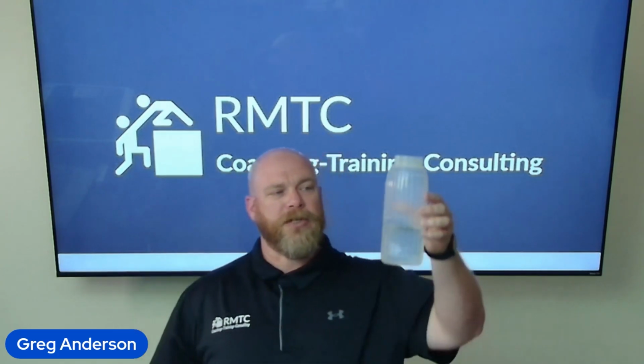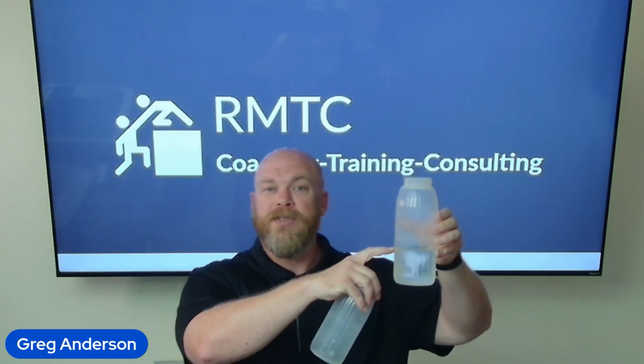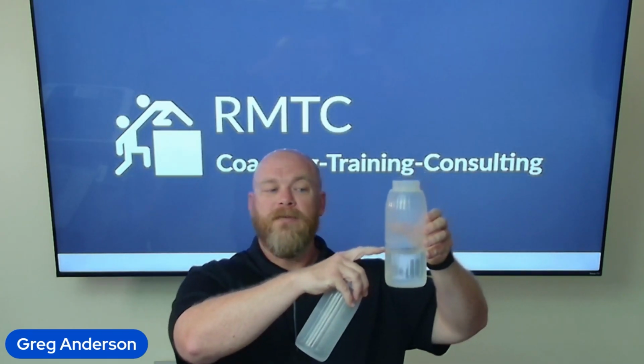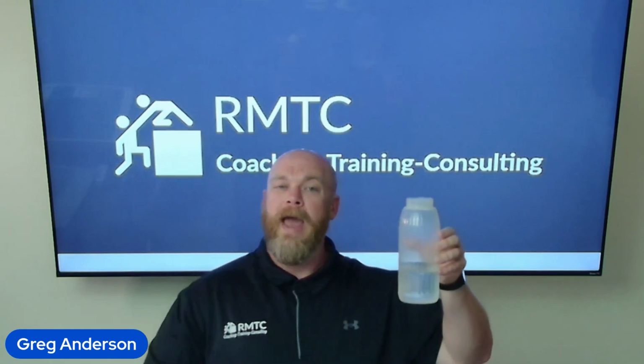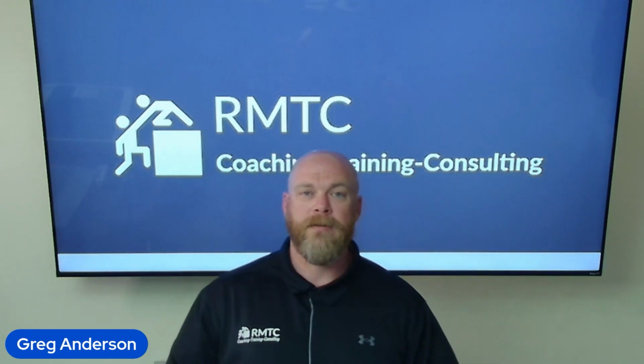If we keep the exact same amount of moisture and just increase the temperature, we can see that the percent full goes down significantly. Now we're down to 25%. 25% relative humidity. We're 25% full compared to how much we could potentially hold at this given temperature.